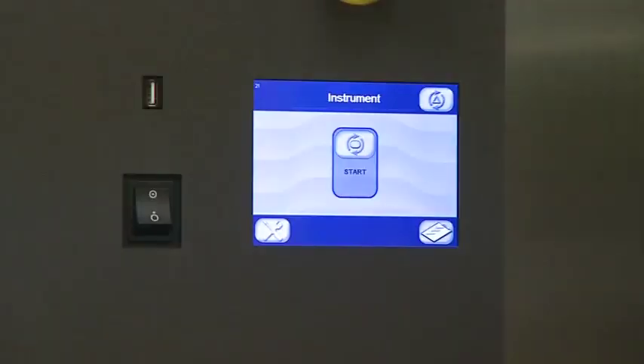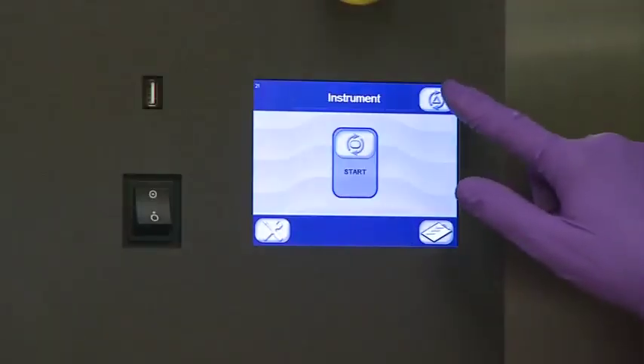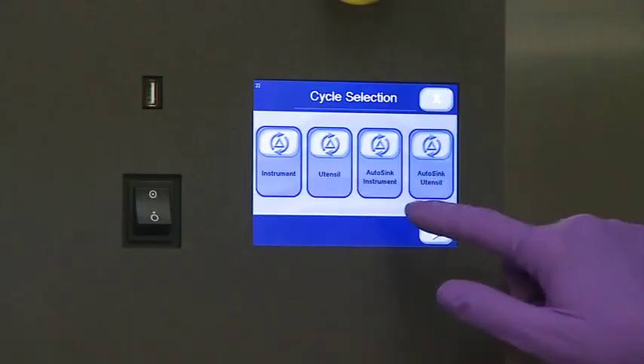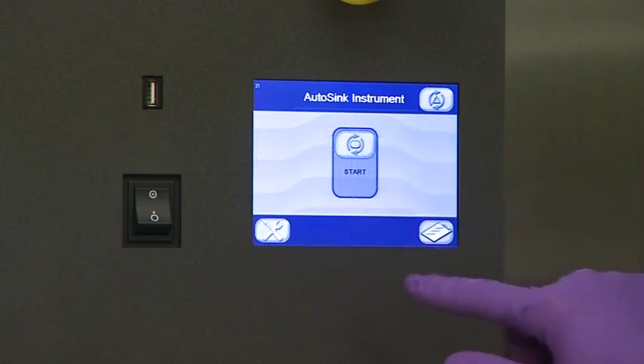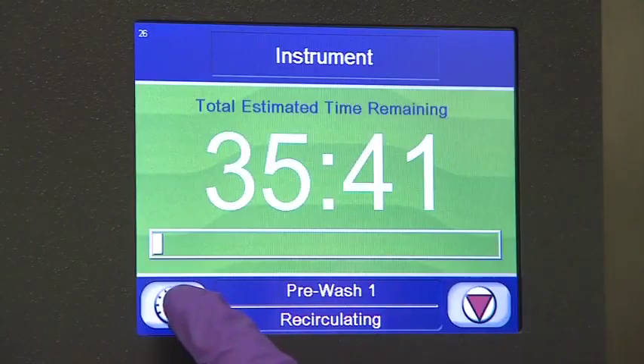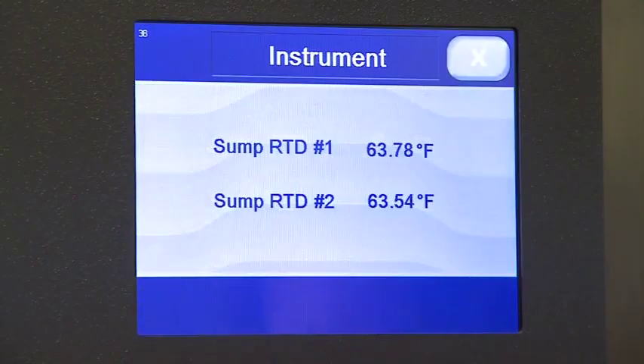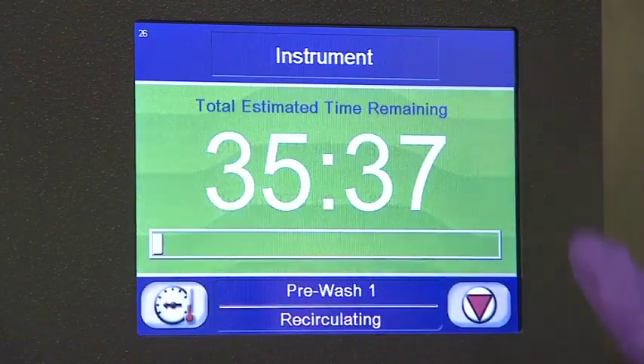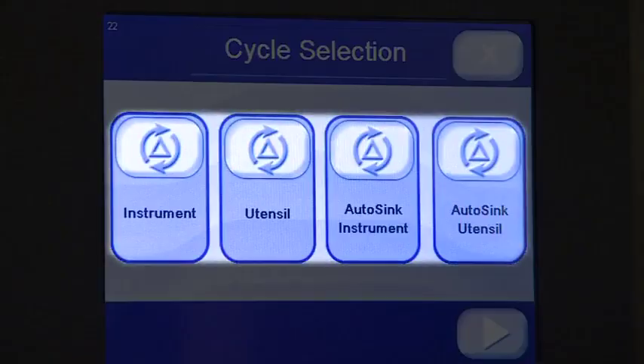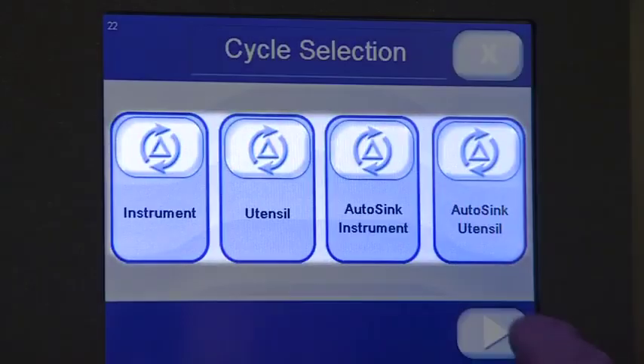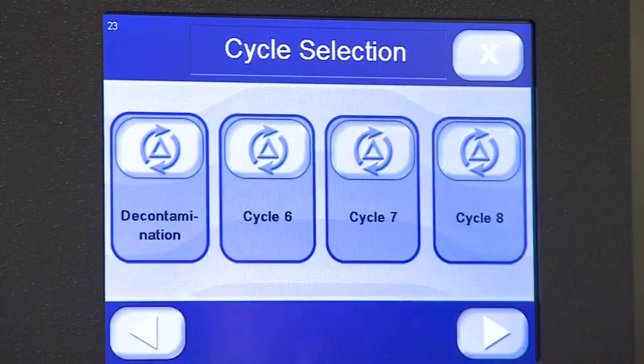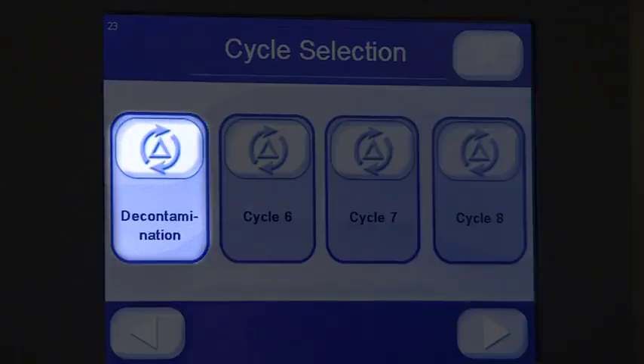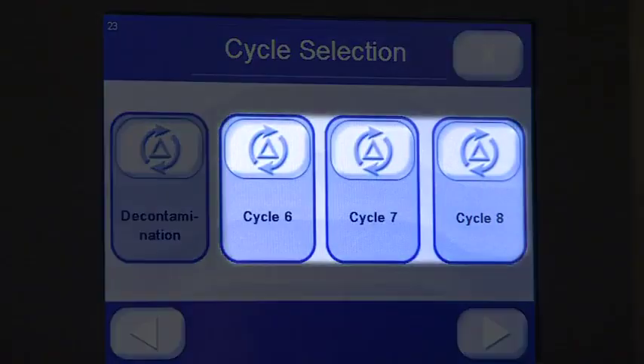Now let's talk more about the control system. The AMSCO 2500 is equipped with an icon-based touchscreen control system that displays current status, the current chamber temperature, and the remaining cycle time. It enables 4 pre-programmed operating cycles for processing a variety of loads, as well as a decontamination cycle. Additional cycles are available for operator custom programming of special cycles.